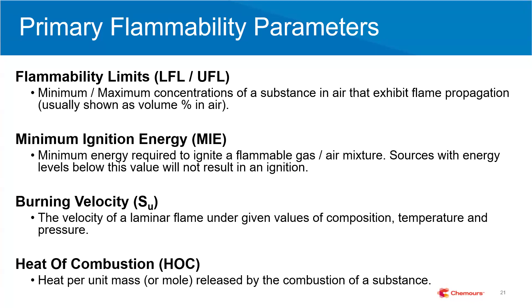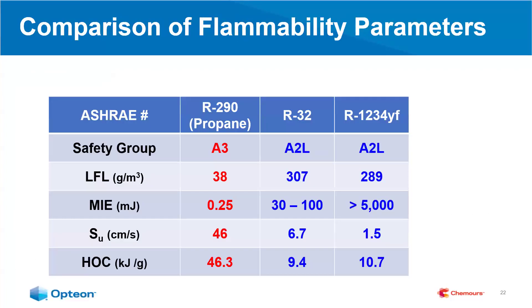If you do get an ignition, then you want to be concerned about burning velocity and heat of combustion. Burning velocity describes how quickly a flame will propagate for a given composition, temperature, and pressure — the faster it propagates, the more severe the ignition event and the higher the rate of pressure rise. Heat of combustion describes how much heat is given off when the refrigerant burns. Now let's take a look at a comparison of these flammability parameters.